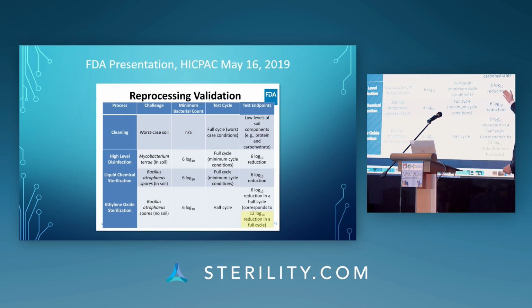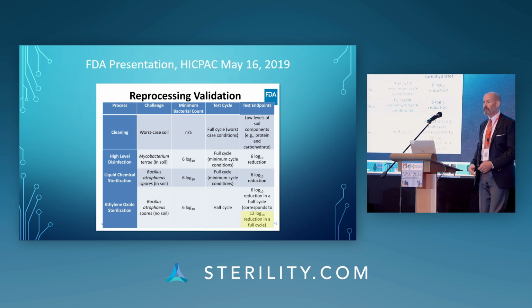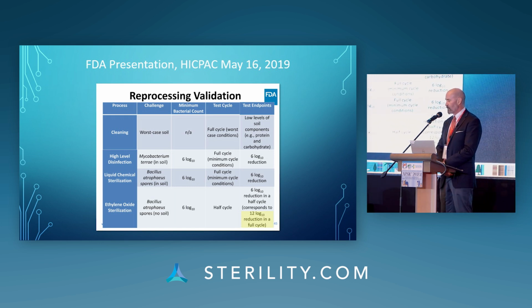You'll see that high-level disinfection and liquid chemical sterilization are capable of achieving a 6-log reduction in bacteria. Ethylene oxide, on the other hand, achieves that in half of its sterilization cycle. In a full cycle, ethylene oxide achieves a 12-log reduction in bacteria. This is what's known as an overkill cycle. This is what is regarded as true sterilization. And I show you this because there is a very significant difference between high-level disinfection and sterilization.